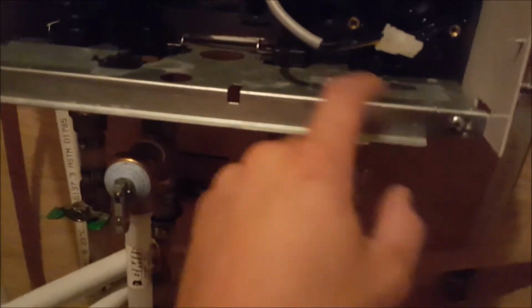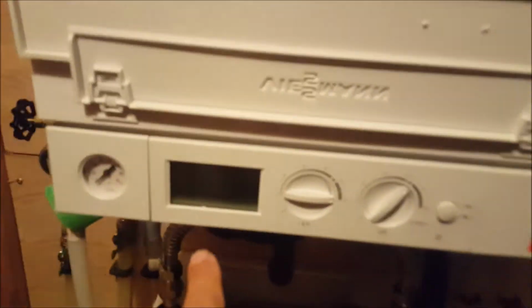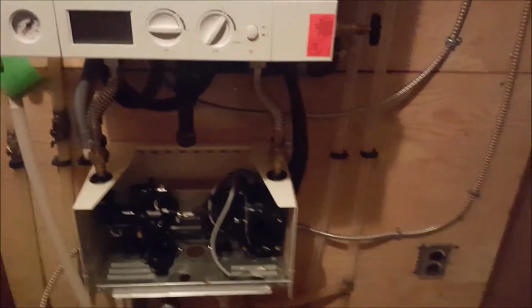So that's why I kind of had a feeling it was in here. I just didn't think it was the pump. But if you look closely, this line connects to the bottom here and goes into this pump housing. I know the light's not very good, but you can see it come out. If this pump's not turning, it's basically acting like a valve to shut off the water, so you have absolutely no flow through the boiler. So the boiler will display that it's trying to run with no error code, but it will never fire up. That's the failure mode in this pump.